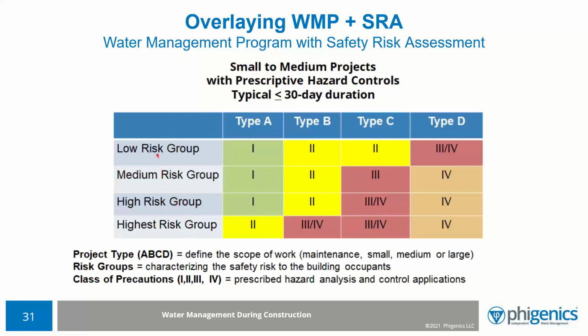In healthcare, they define them into 4 risk groups. In education, we've had folks define them into 2 risk groups, low risk and high risk, based on the building types around the campus. For instance, a high risk could be a dormitory, overnight stay, or where there's showering, athletic facilities, or a student infirmary—those might be higher risk spaces than, for instance, offices or classrooms where you may have very little water in certain areas and you're going to do a renovation.